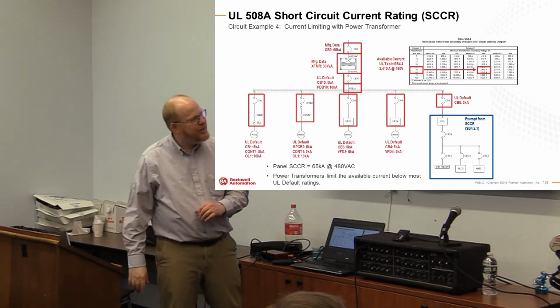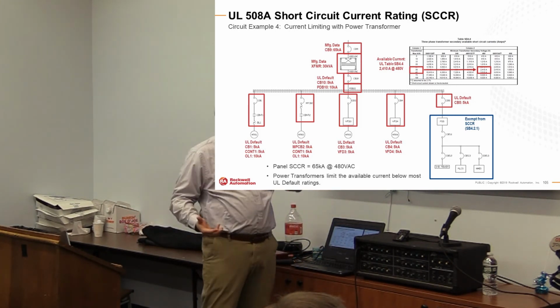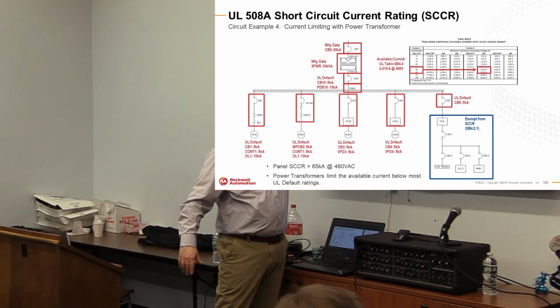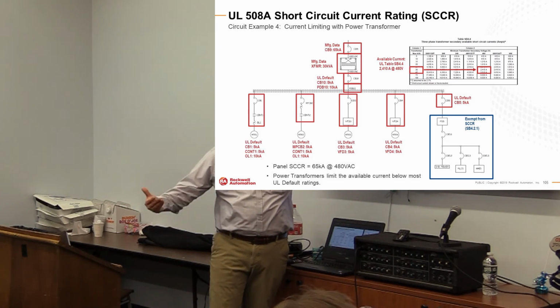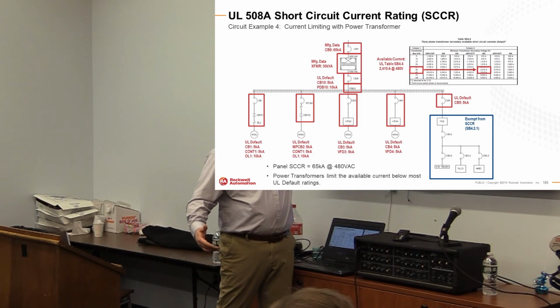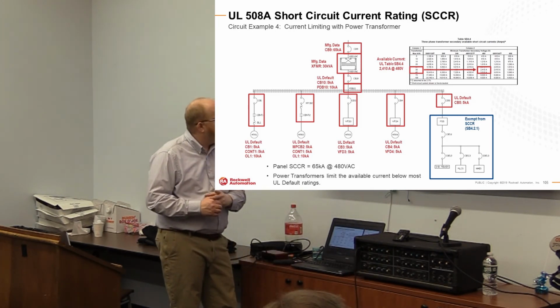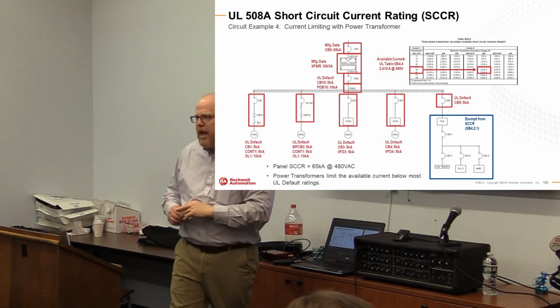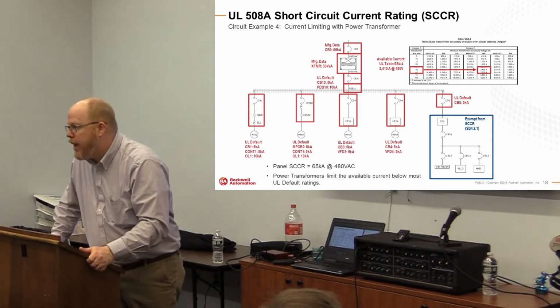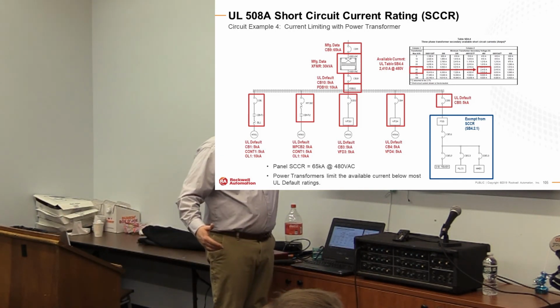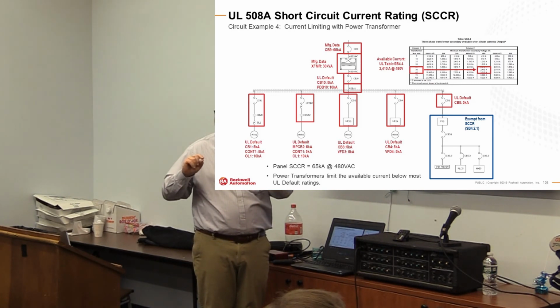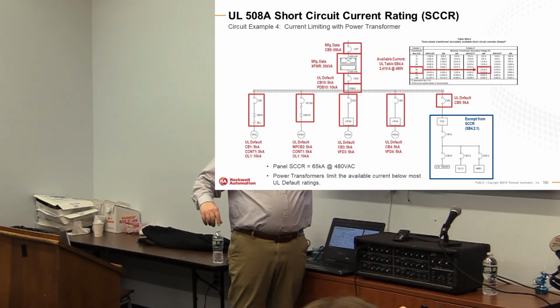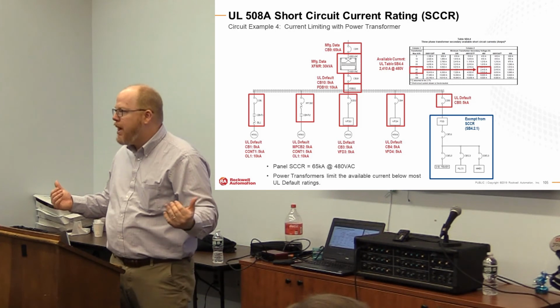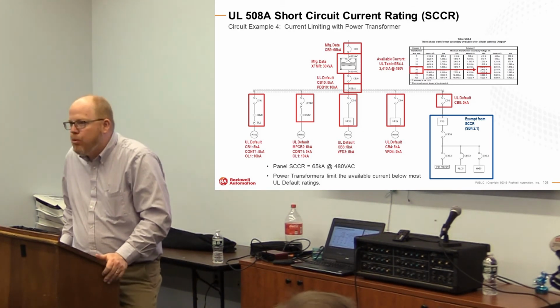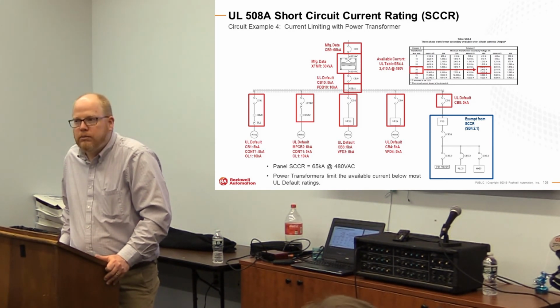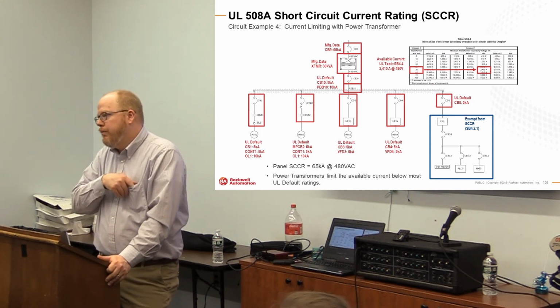So we can kind of talk about this in two scenarios. Number one is if indeed you did put it in the box. The whole panel would carry 65, because all of my branches down below past the transformer are well above the 2.4 kA, even at default. In which case, you're limiting yourself to the main circuit breaker number 9 there, so you could claim 65. So then the guy proceeded to say, yeah, but what if that transformer was separate from the panel? Like, say, a lug-only panel? Okay, well then what I would put on this panel is 5 kA on the box, but I would reference the fact that the upstream current limiting is achieved from a 30 kVA transformer, and the peak let through of that guy is only 2.4. So we're back to the fact that a default 5 kA is more than sufficient to meet the peak let through of this scenario. So however you want to skin that cat is a reasonable way to do it. All right.